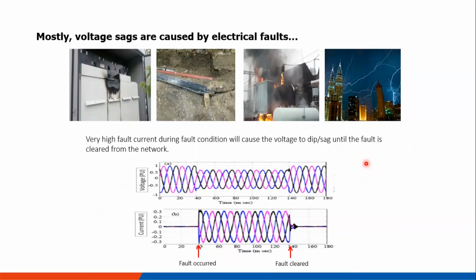Mostly voltage sags are caused by electrical faults. As you can see here, this is a switchgear. They have some fault in it. There's a burning fault, a burning color here. Yeah, an underground cable joint, some fault here. Flashover of equipment, the transformer flashover, and lastly, the lightning strike. Lightning strike can cause voltage sag.